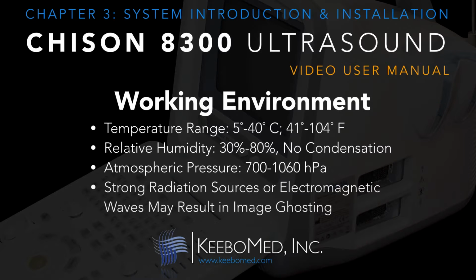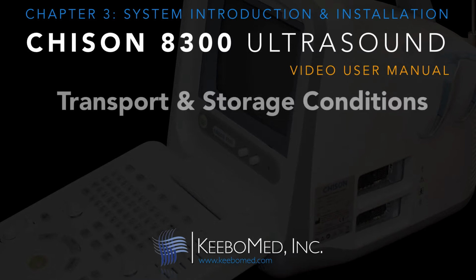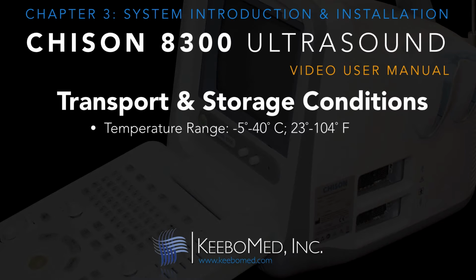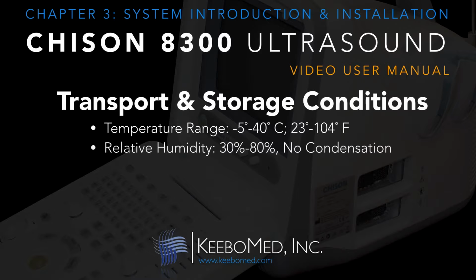Strong radiation sources or powerful electromagnetic waves may result in image ghosting or noise. The system should be isolated from such radiation sources or electromagnetic waves. Transportation and storage of the 8300 is best if it is kept within the system tolerances. The approximate temperature range should be -5 degrees to 40 degrees Celsius or 23 degrees to 104 degrees Fahrenheit, and a relative humidity of 30% to 80% with no condensation. The atmospheric pressure would range from approximately 86 to 106 kPa.